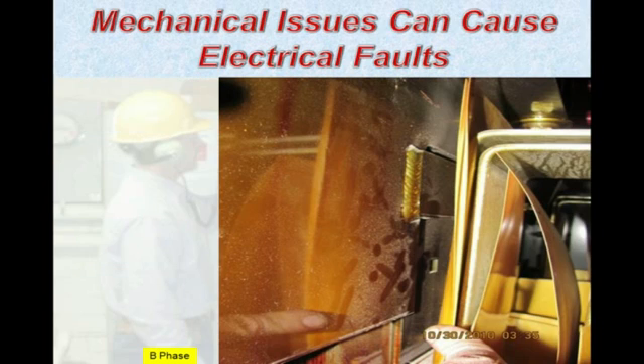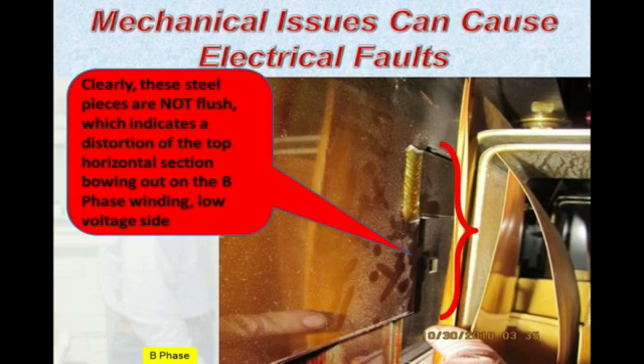On the suspect coil, though, we can see in this image, if you look closely, there is clear evidence that the horizontal steel is not flush with the vertical steel here where the weld is made. This is causing the top horizontal section to bow out on the low voltage winding on the B-phase side. And right where the call-out arrow is pointing, you should be able to see the elevation difference between the two pieces of steel. This is a problem.